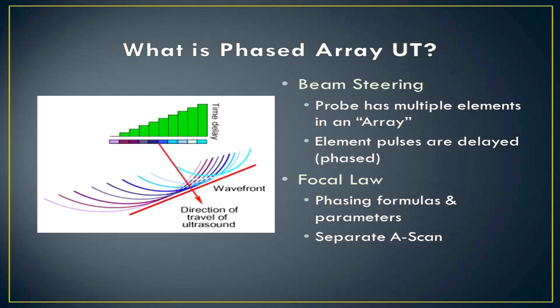So basically the principle behind phased array is you're able to electronically steer the beam, as opposed to conventional UT where the beam is fixed. This allows a lot of flexibility in this method. The probe that we use has multiple elements, arranged in an array. The element pulses are delayed or phased from each other, and the wavelets generated by each element form into a single wavefront, and the direction of travel of that wavefront is dictated by the phasing delay.